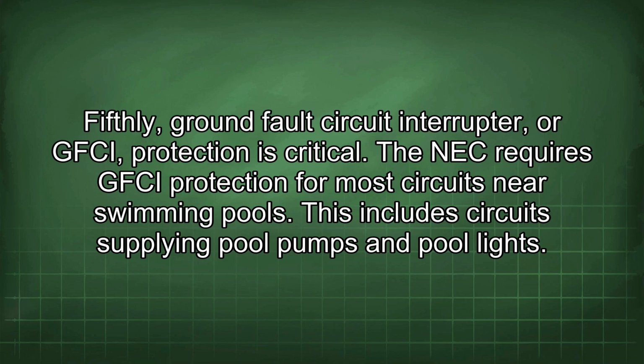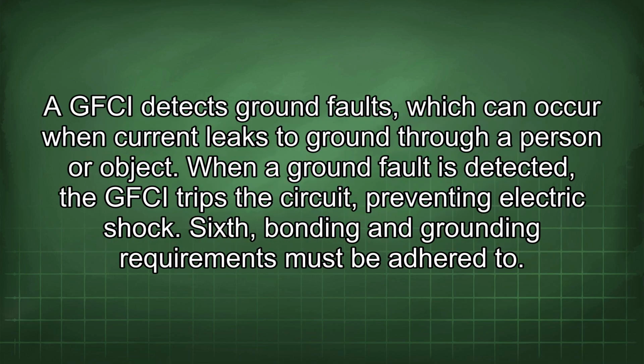Fifthly, ground fault circuit interrupter, or GFCI, protection is critical. The NEC requires GFCI protection for most circuits near swimming pools. This includes circuits supplying pool pumps and pool lights. A GFCI detects ground faults, which can occur when current leaks to ground through a person or object. When a ground fault is detected, the GFCI trips the circuit, preventing electric shock.